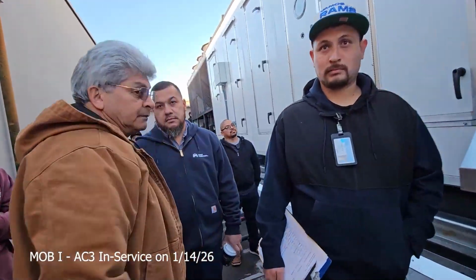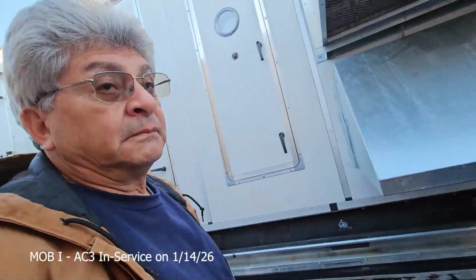I have a question on changing filters. Can I partially shut down instead of shutting down the whole unit to change the filter? Can you show me how? Remember when I said your boss is going to dictate that? I would not want to change filters on this machine personally without shutting the fans down. Well, can I shut the fan with the breakers inside of the compartment? You're going to create an issue. Remember I told you that these fans like all running at the same time?